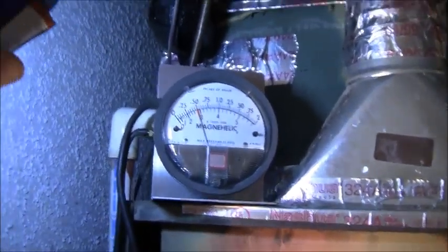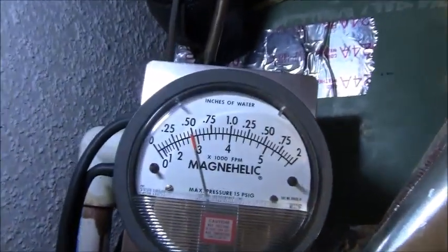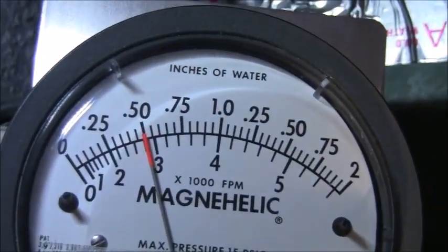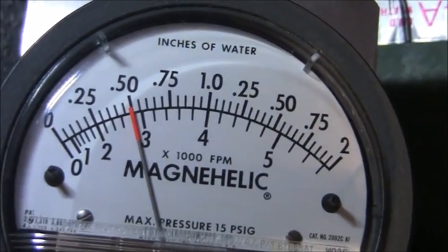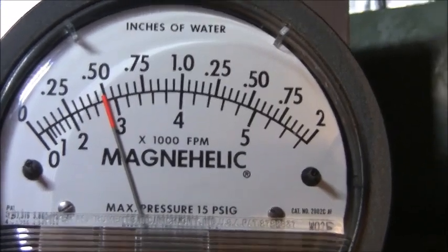Okay, and then on the high side of the Magnehelic gauge, which is the top line, I got that coming down, and that is plugged into right there, which is on the upstream side of the AC coil. There is your external static pressure on the Magnehelic gauge. That is at 0.5 inches. That's a half of an inch of static pressure, water column. That is a good static pressure. This unit is breathing, and it is allowing the proper amount of airflow with the fan in heating for CFM. Okay, now that I know that the unit is breathing appropriately, the AC unit has good airflow in heating mode. My expectation is to be the same thing in cooling mode, same thing with the airflow, but we'll verify that once we get to cooling.